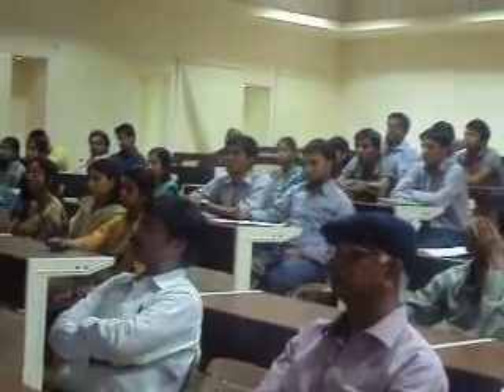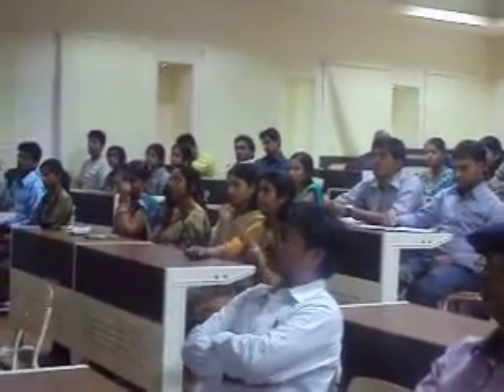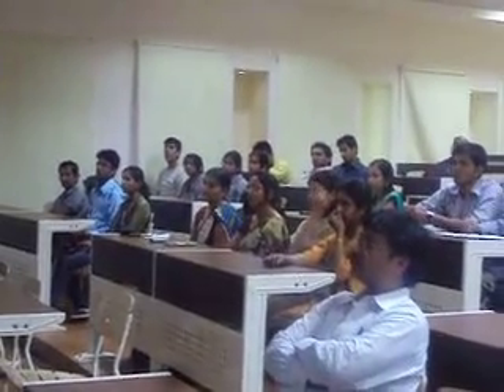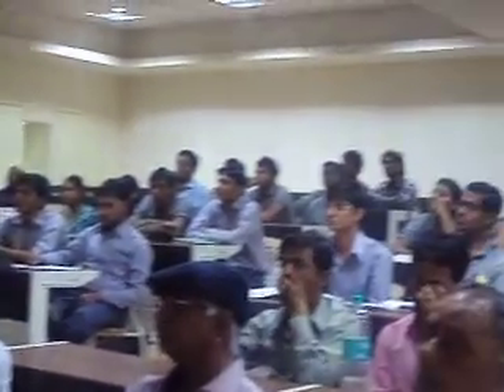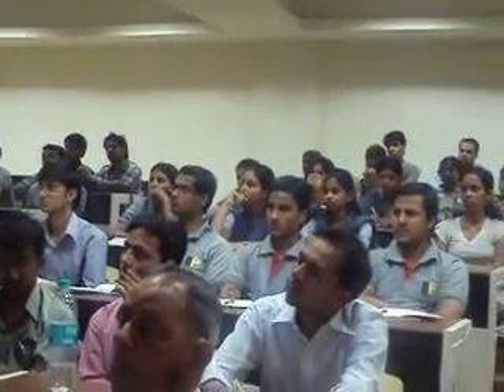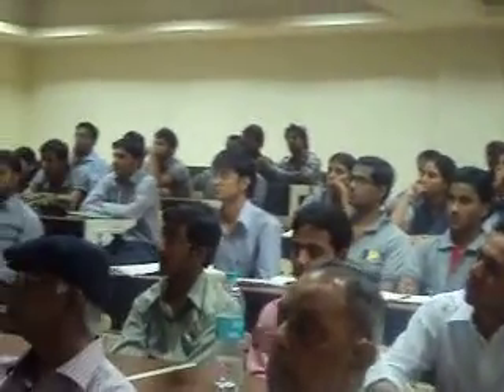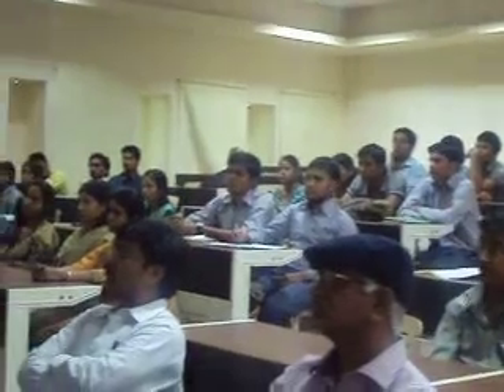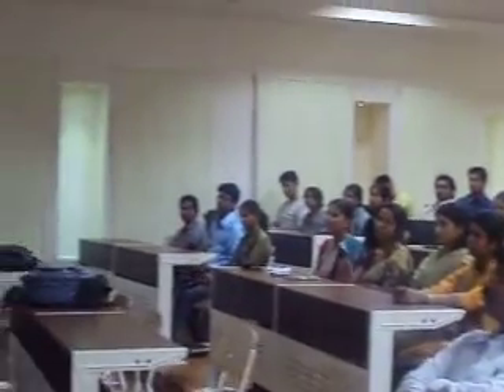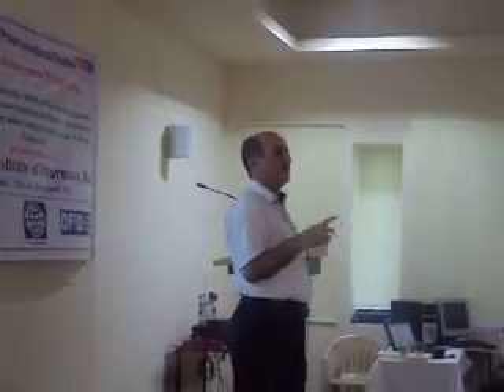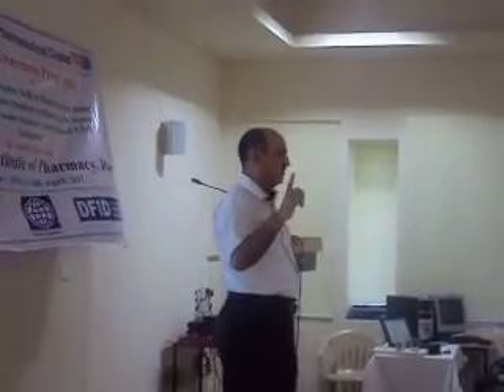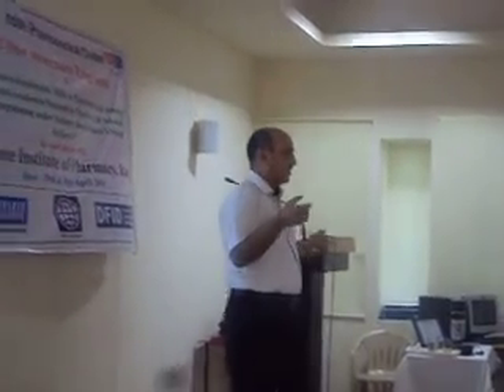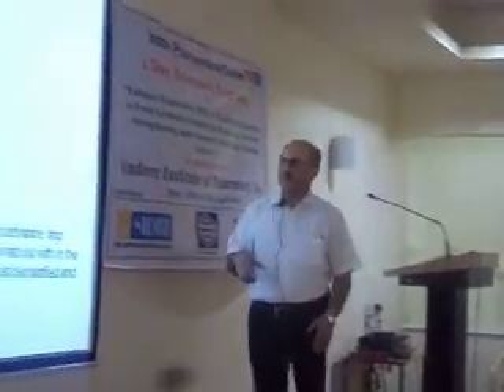Then we have air changes, pressure differential, and filter qualification. Air changes is generally a term used for those areas where we have air handling units, like in microbiology, where we need to periodically check the number of air changes happening per hour. Generally, the number of air changes in the room is measured per hour, meaning how many times the volume of the room is changed in an hour. This is measured for those rooms where air handling units are provided.